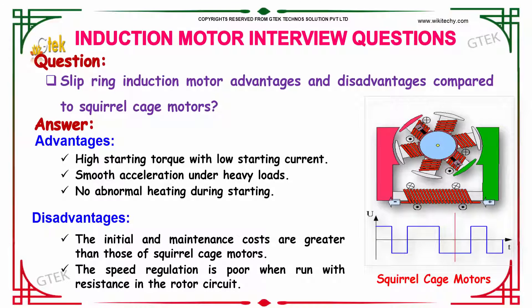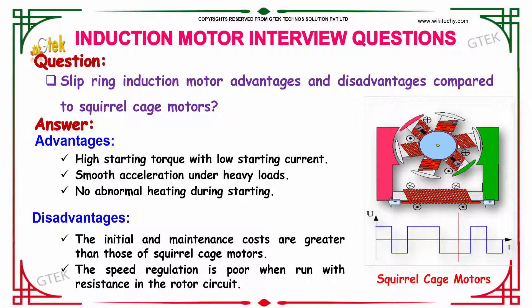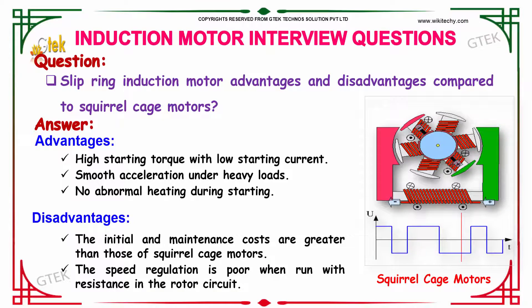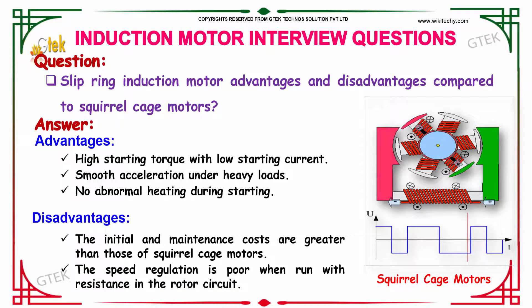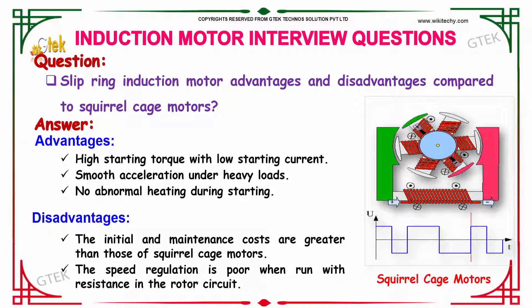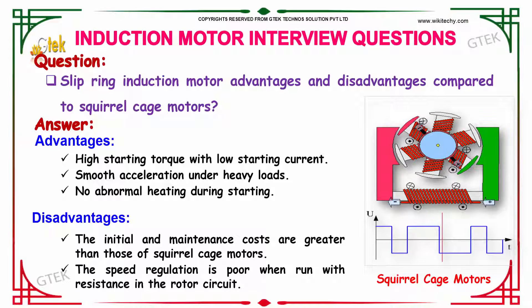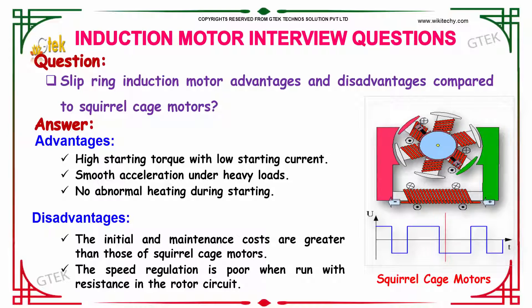These are the advantages. Looking at the disadvantages, the first is that the initial and maintenance costs are greater than those of squirrel cage motors. The second is that speed regulation is poor when run with resistance in the rotor circuit. This covers the comparison of advantages and disadvantages of the slip ring induction motor versus squirrel cage motors.